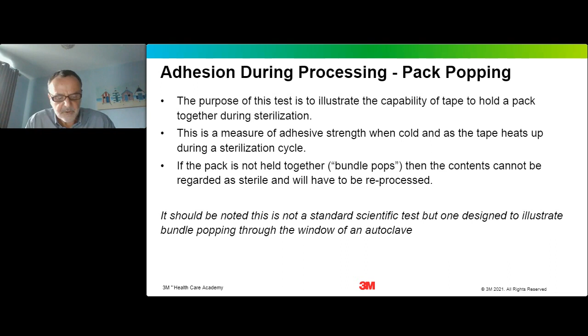Two points I must note. The first is that if the tape pops then the pack cannot be regarded as sterile. So this is an undesirable consequence of poor adhesion, because if packs pop open during sterilization, it means they have to be reprocessed. The second is that the video I'm about to show you is not really a scientifically developed test, but it is merely used for illustration purposes. So don't draw too many strong conclusions from the results.